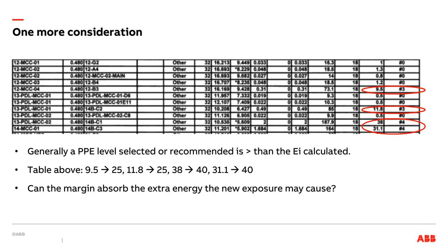And here's an example of an arc flash study, and they use the term hazard risk categories, by the way, which is why you see the number 3, number 4 here. And notice here they calculate 9.5 calories, but they're using number 3. Number 3, as we all know, is 25 calories. That's quite a bit of margin. Here they calculated 11.8, I think. Again, 3. Here they calculated 31.1. They went to 4, which is 40 calories. There's a margin between this column and that column. So the question at the end of the day is, is that margin enough per my decisions on acceptance or non-acceptance of risk relative to what a new arc flash calculation would yield? How do I determine that without going through the full process of a new arc flash calculation?